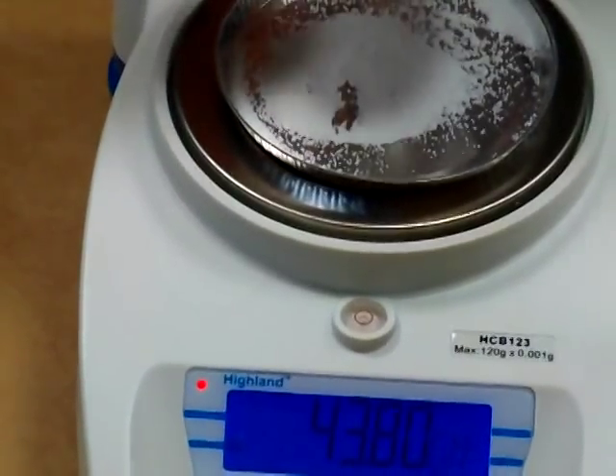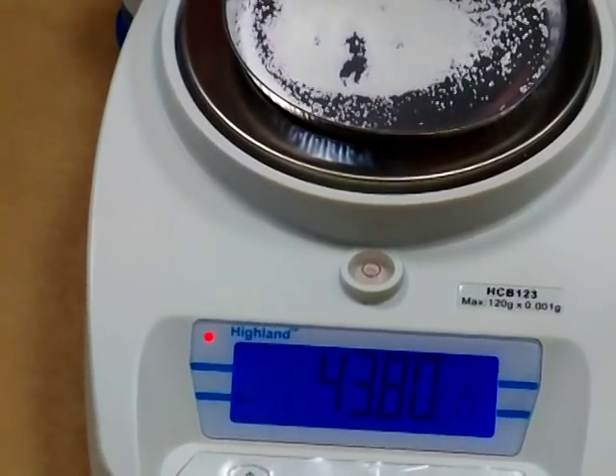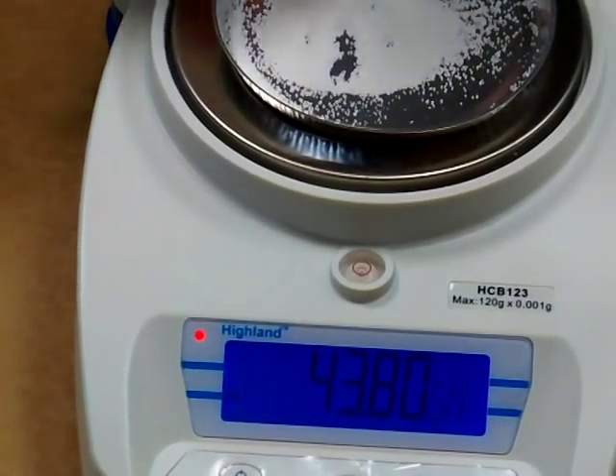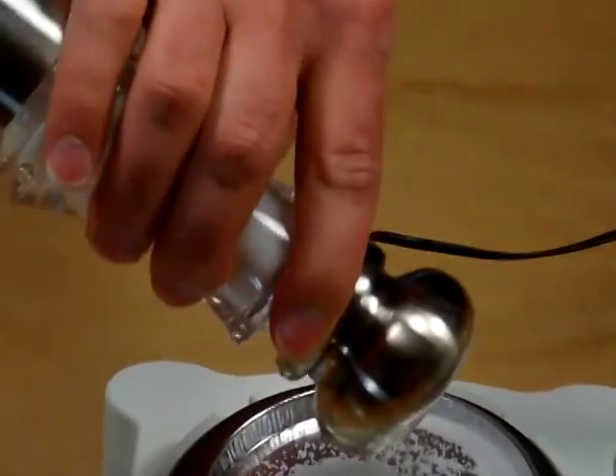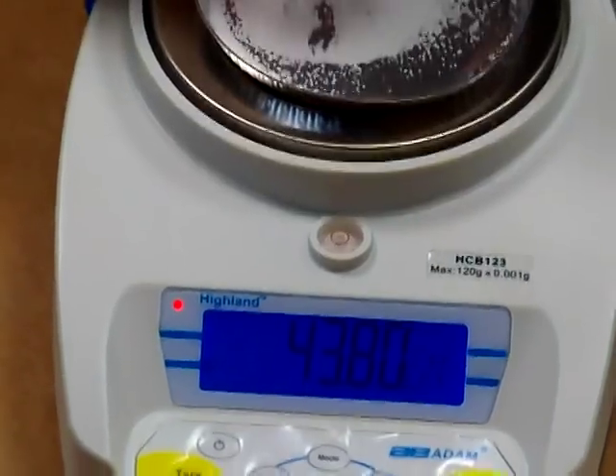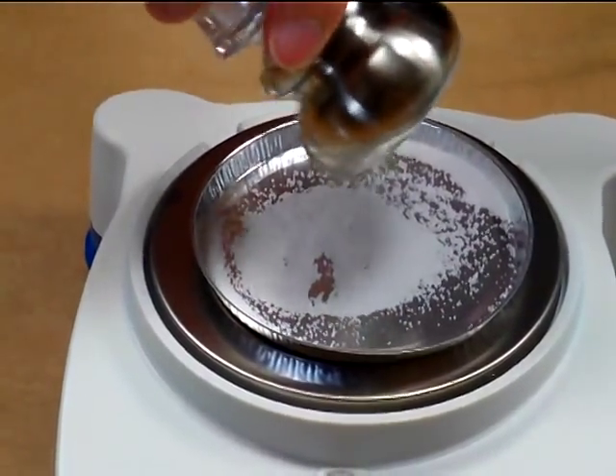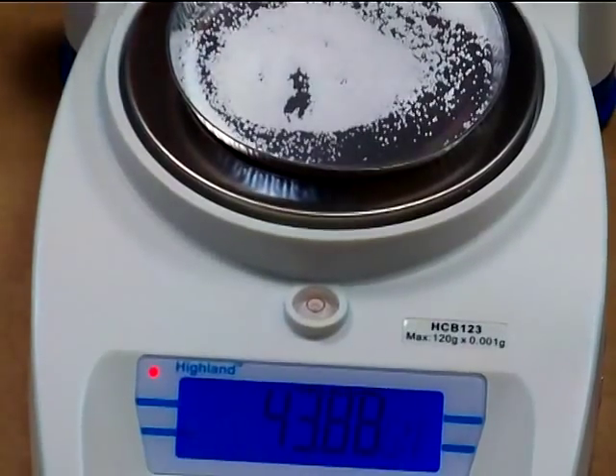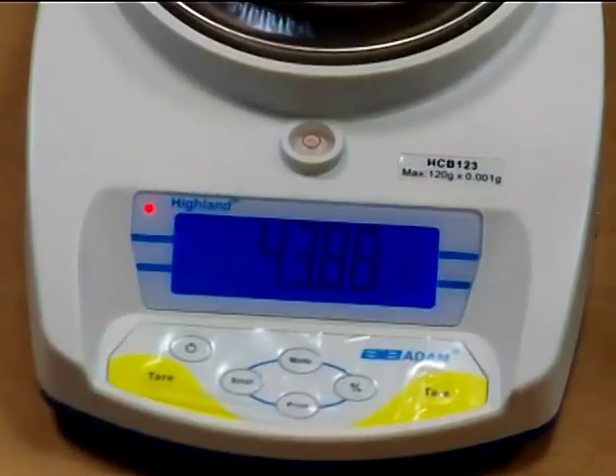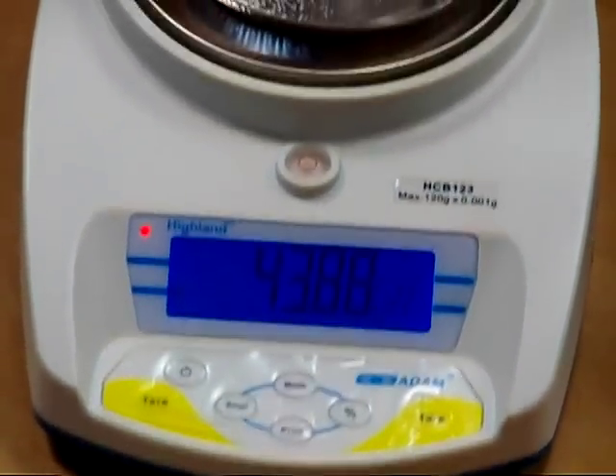So I'm going to add a little bit more salt — you can see the response time is very, very slow and it's not very responsive. If I go slow and put like ten grains of salt on at a time and stop, add, stop, add — the balance wouldn't even record any of it whatsoever.